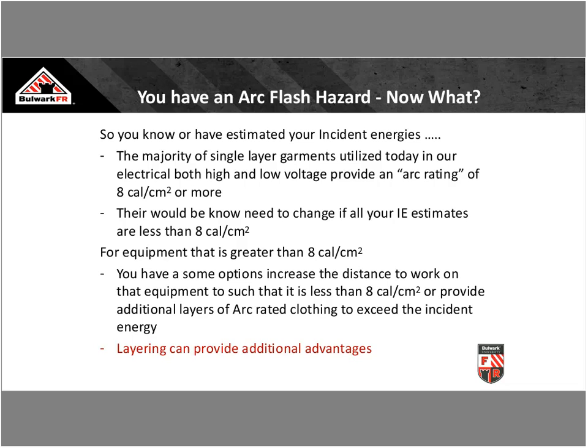Well, there's a couple things you can do. One is you can get further away. Remember, most of these default calculations are done primarily at about 18 inches. Why 18 inches? That's the distance between my chest and the energized electrical equipment, approximately. And that's the default distance for the large majority of calculations. That being said, what can I do then? Well, I can get further away. I can operate it remotely. I can operate it at the end of a hot stick. I can operate it to where whatever I need to do, I'm not in front of that piece of equipment. I've created engineering to where I can access it and not be exposed.